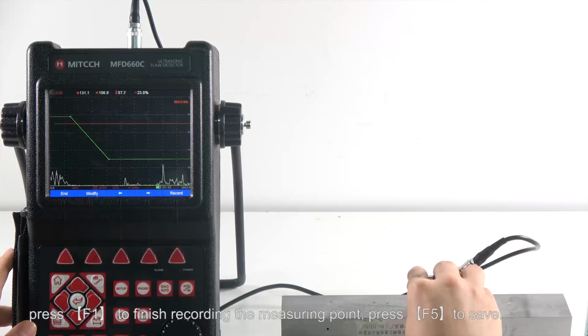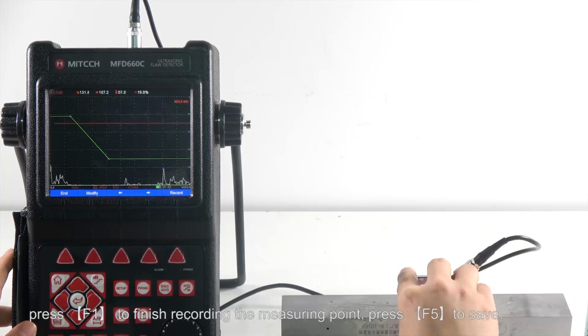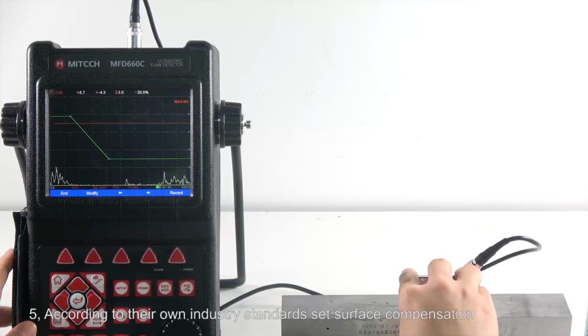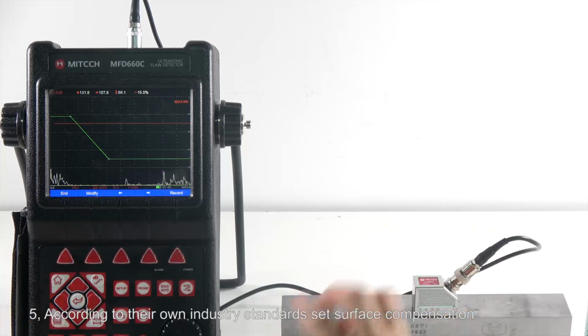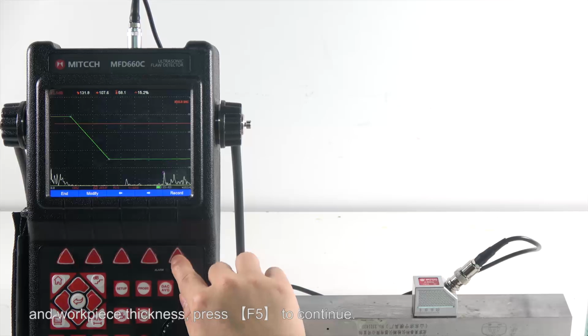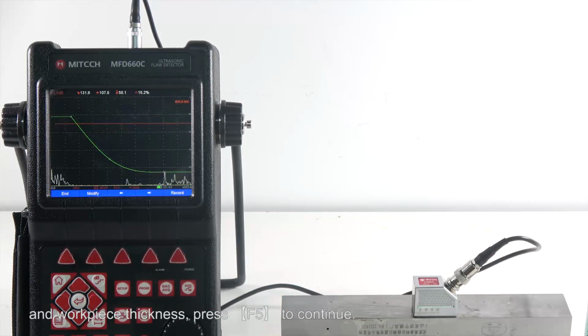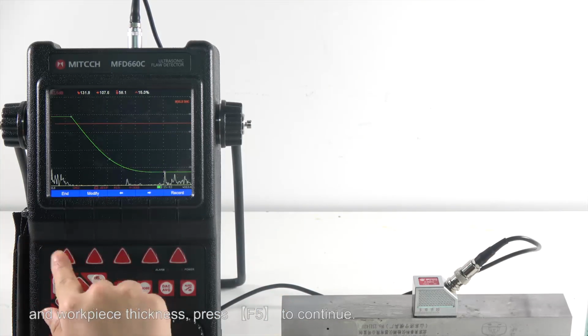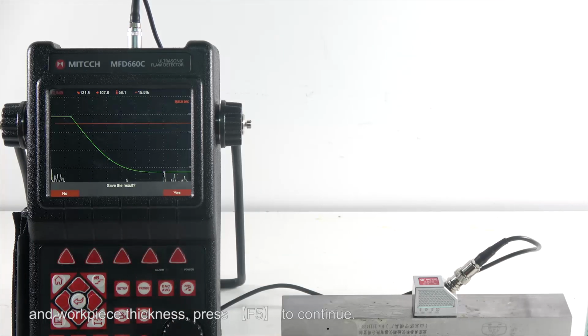Press F1 to finish recording the measurement points. Press F5 to save. According to your own industry standards, set the surface compensation and workpiece thickness. Press F5 to continue.